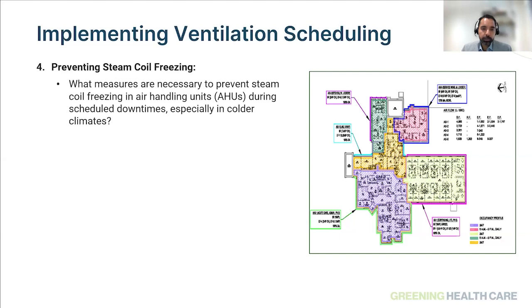There are provisions in your control sequence of operations that you can make it happen. You don't have to go aggressive in certain cases where the infrastructure is old. You can schedule your systems for a certain period of time when the outside air weather conditions are right, so that supports the non-freezing of the coil. For the rest of the weather conditions, you can let the system run. But it's a case-by-case basis, and there's not a complete either-or in this case. It's an approach that takes into account the provisions for making sure that the system is safe to operate, and the hours that it is safe to operate.